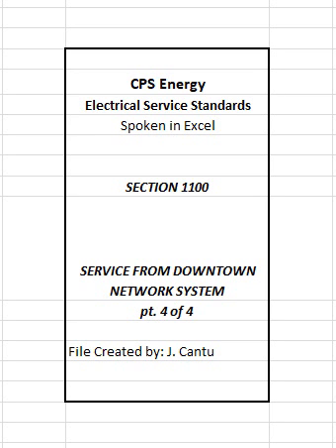A. Fault current rating. Customer-owned service disconnecting means shall be rated for the available fault current as determined by the CPS Energy customer service representative at time of design and shall be installed in accordance with the NEC and all applicable codes, refer to section 400. Customer shall design service with consideration for future fluctuations in fault current that may result from customer loads changing on the downtown network system. Upon request, CPS Energy will make available fault current information.